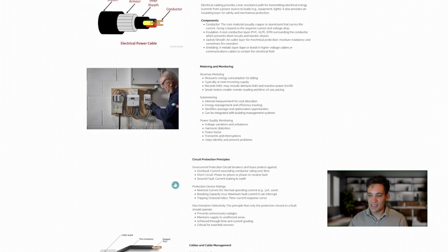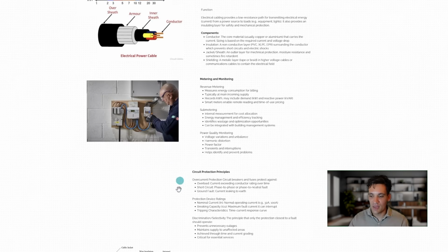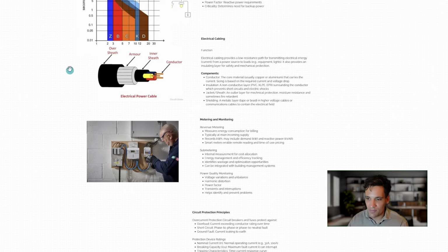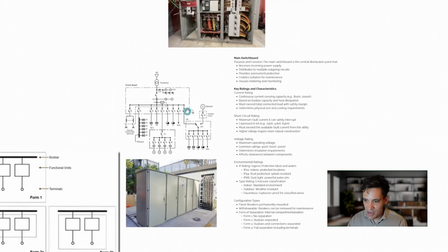So all circuit breakers have this time current performance curve, and electrical designers will choose the correct circuit breaker so that the downstream circuit breakers trip before the upstream. What does this mean? So we look at our electrical system, which is the main circuit breaker, which is the single line diagram. If we get a fault on this motor, we want this circuit breaker to trip before this circuit breaker. If this circuit breaker trips before that one, it means when we get a fault on that motor, we lose power to our entire facility.